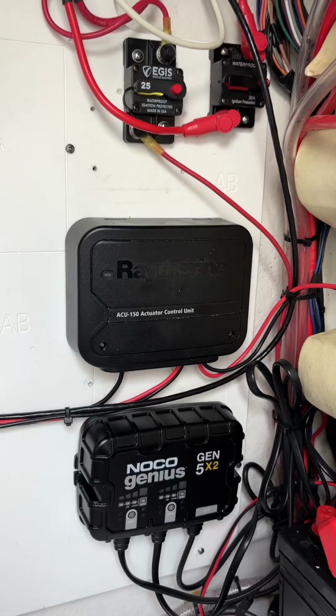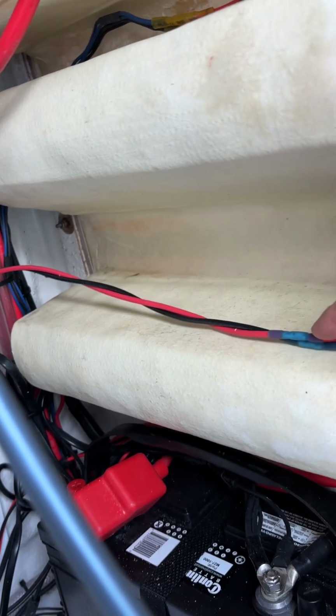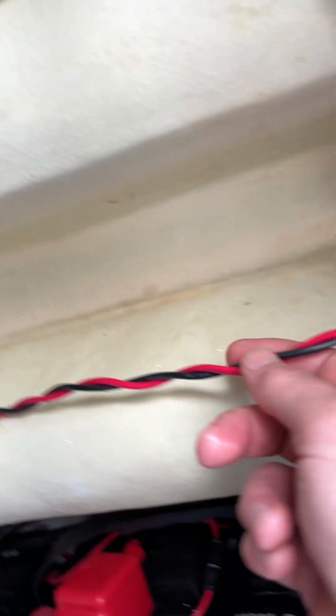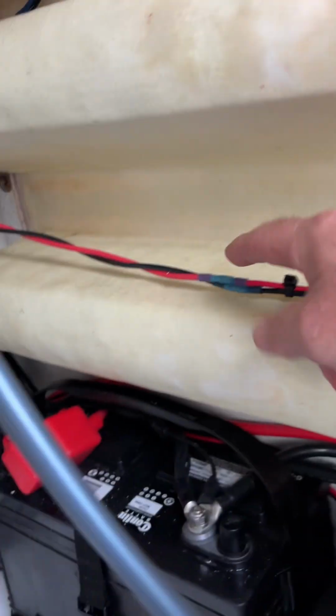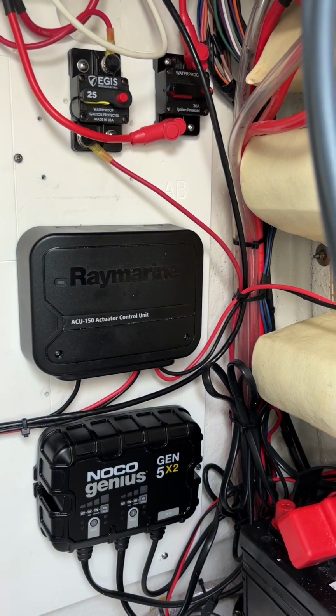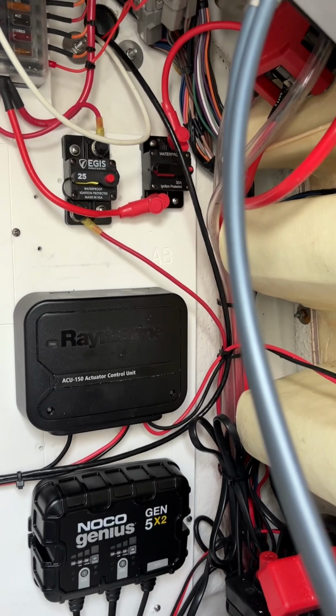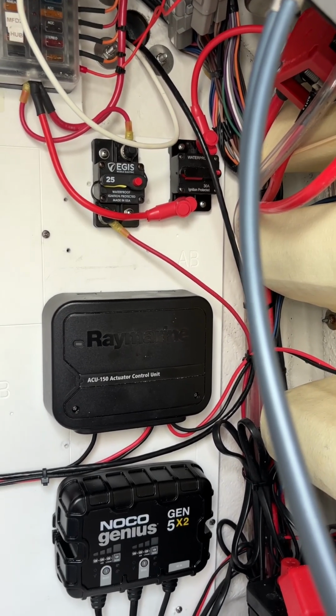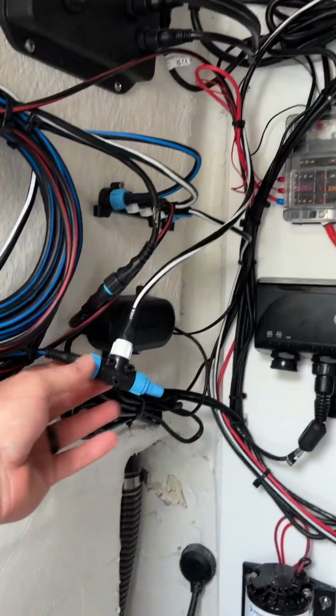Try to keep your control unit as close as you can to the pump — the cable is only so long. I had to extend it for my installation. This is 14-gauge wire from the pump, which I tied into 12-gauge so I wouldn't get any current loss going to the pump and into the control unit.